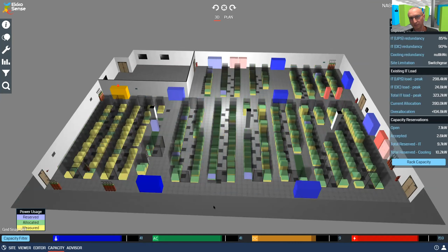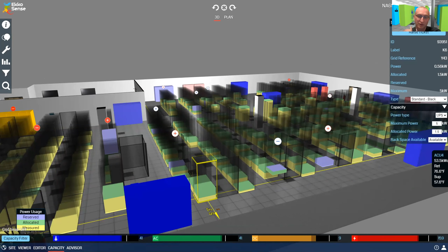We can collect power data via Modbus and SNMP, typically for individual racks. So you'll see everything, the racks are sharing the power views available. If I click onto this rack, you can see power attributed to the rack and how much has actually been allocated to it. You can manage those allocations, the maximum power for different types of rack, the actual power type, and how that's linked back to the PDUs themselves.